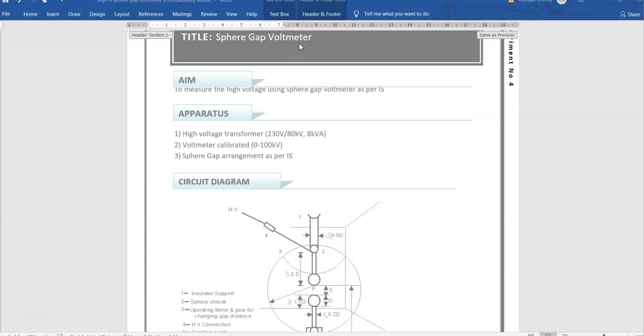One complete unit is there, the fourth unit is on measurement of high voltage. In measurement of high voltage we'll see this method, how we can use only two simple sphere gaps for measurement of unknown voltage. So this experiment will be conducted, but even if our objective is different, the experiment will be done the same way. Keep a certain gap distance between the electrodes and find out the breakdown strength of air. Afterwards we will see how we can use those readings for finding the unknown voltage, and whether we can use two spheres for measurement of unknown voltage or not. So that is the objective. But how we can use two spheres for measurement of unknown voltage, that we will see today.